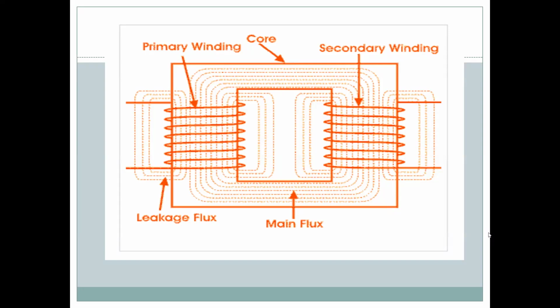We try to ensure that when a transformer is not running on load, or is running on load, its losses are minimum. So we try to invent some kind of metallurgical development in this steel so that it has no loss when it is not working fully, so it is minimum in nature. So the engineering is still going on to find the particular steel which will give you minimum losses. Sometimes we have gone beyond steel to another alloy metal called amorphous, which gives low no-load loss. So even when the transformer does not work, it will consume less loss. So that was the fundamental of how to reduce the losses, because our transmission losses are very, very costly.